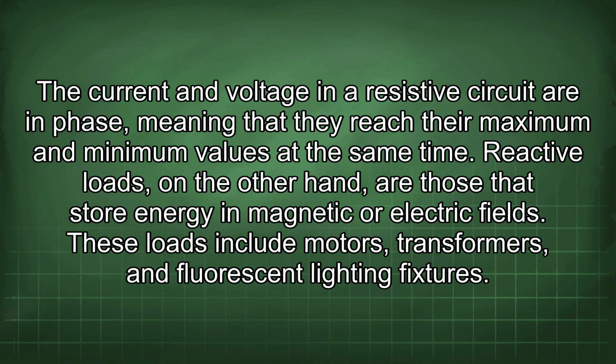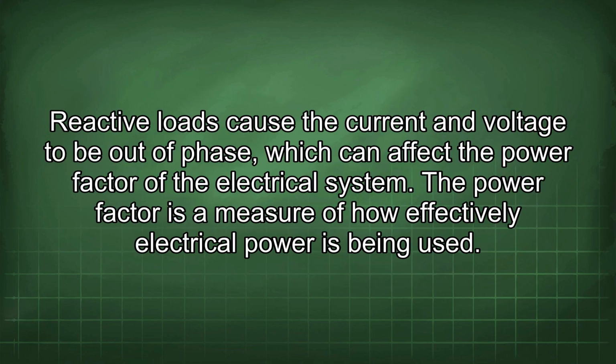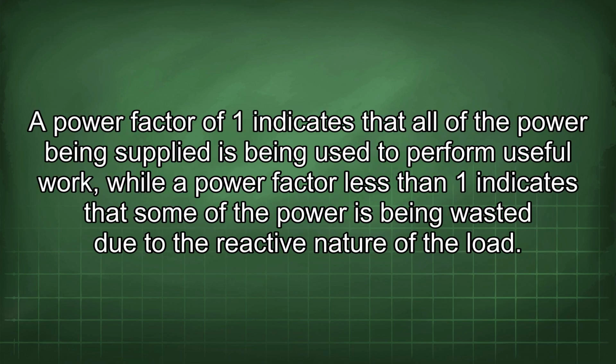at the same time. Reactive loads, on the other hand, are those that store energy in magnetic or electric fields. These loads include motors, transformers, and fluorescent lighting fixtures. Reactive loads cause the current and voltage to be out of phase, which could affect the power factor of the electrical system. The power factor is a measure of how effectively electrical power is being used.